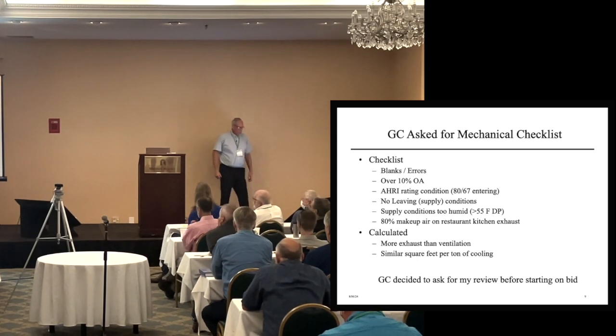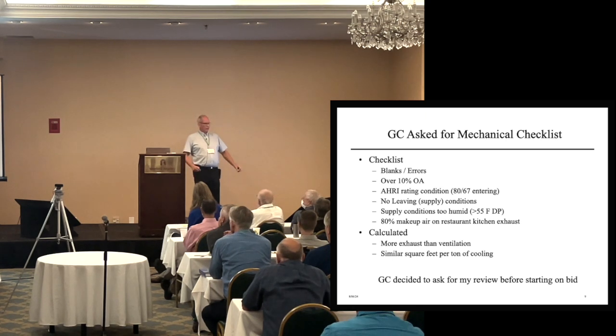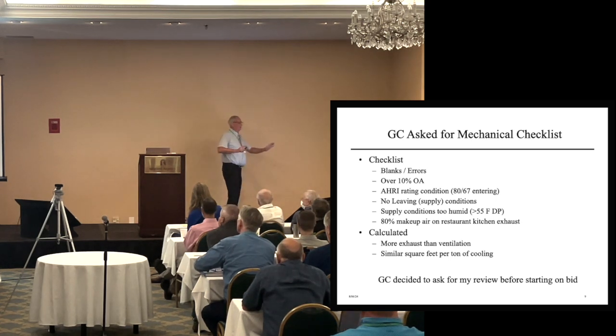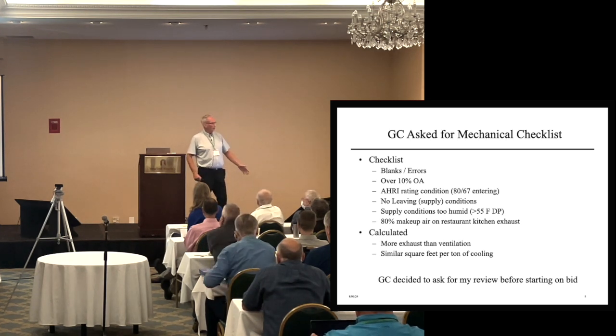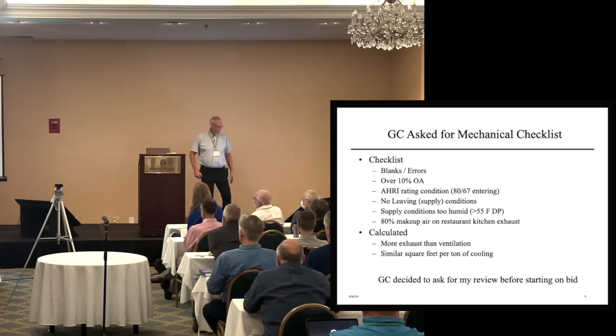And then, because he was doing a lot of restaurants, if you see 80% or more makeup air on a restaurant kitchen, they just use the rule of thumb, always 80%. I hesitate to go too deep into this because that's a whole separate presentation, but let's just say 80% is the worst case condition, and it starts to cause all kinds of problems if you see that, okay?